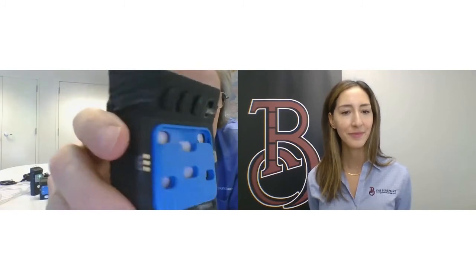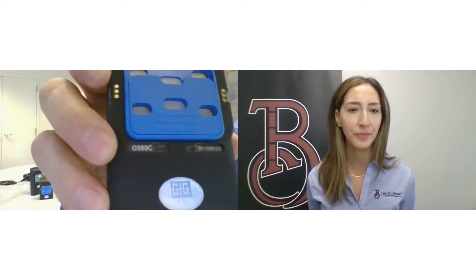Well, PIDs take a bunch of power, so we don't make the PID available in the 888. In fact, you can tell if the 999 is one that has been set up on the board for use with a PID sensor. It will say on the front of the instrument G999P, just like this instrument. Actually, you can see it says G999C. If this was a PID option instrument, it would have a P at the end of the product part number. So we actually build the board for PID equipped instruments a little bit differently, where one of the positions is permanently dedicated to having a PID sensor.